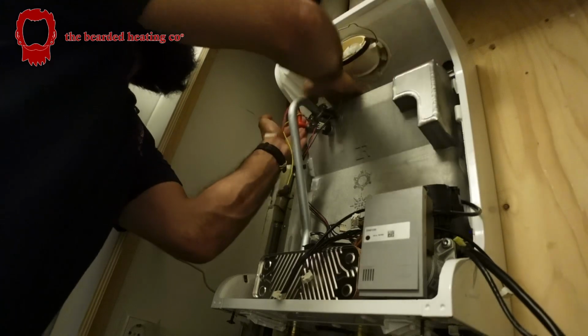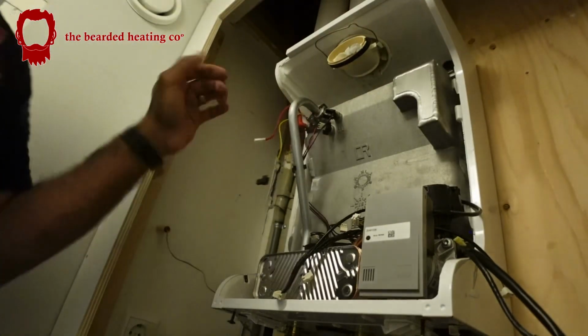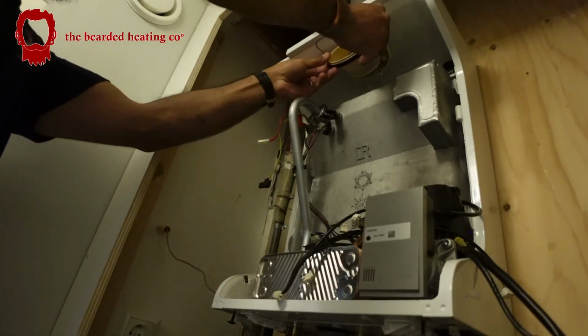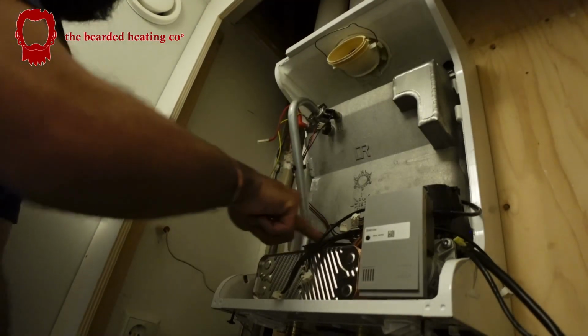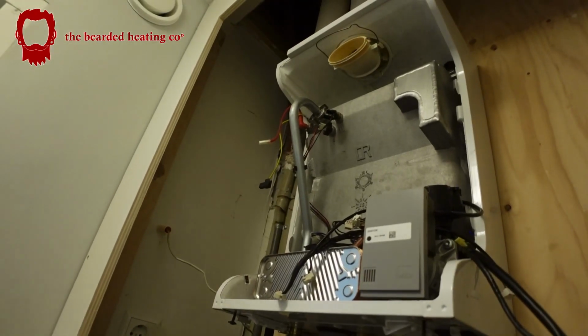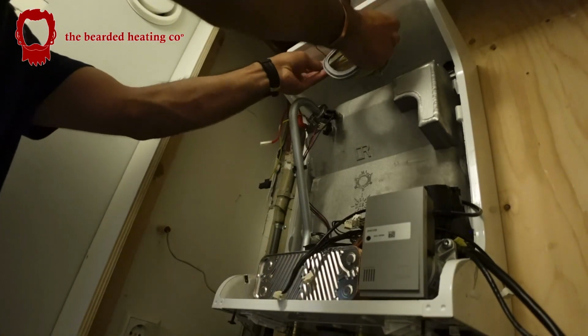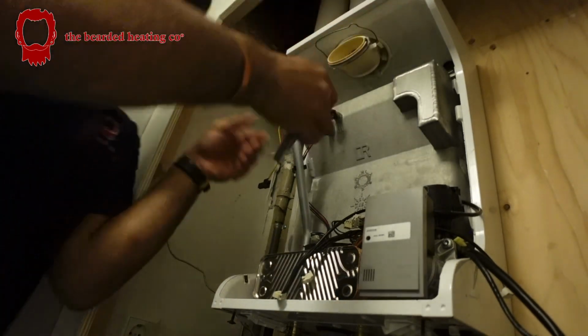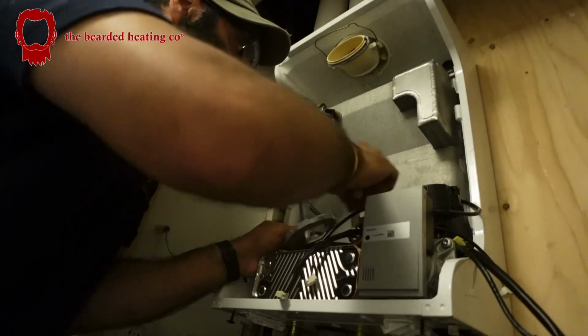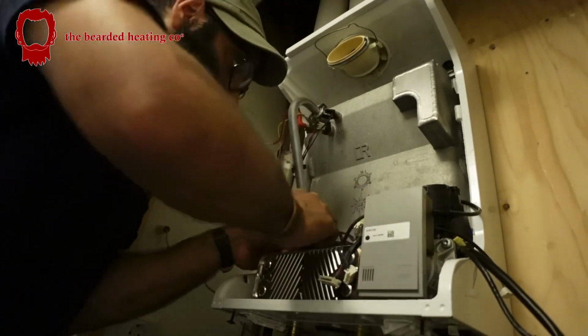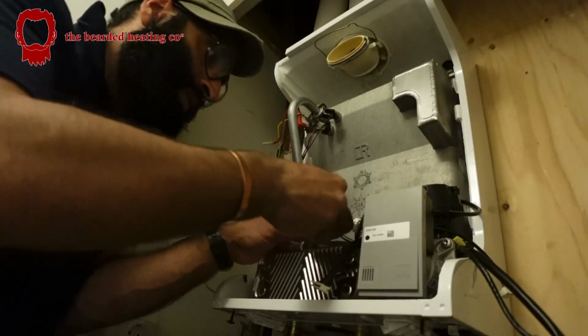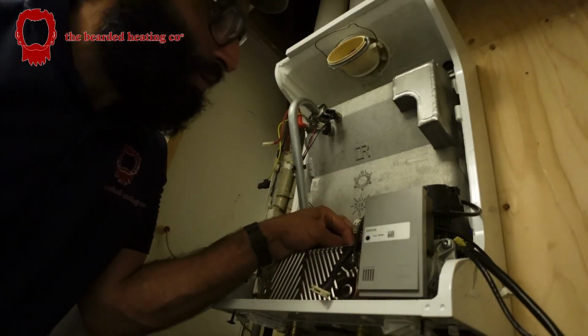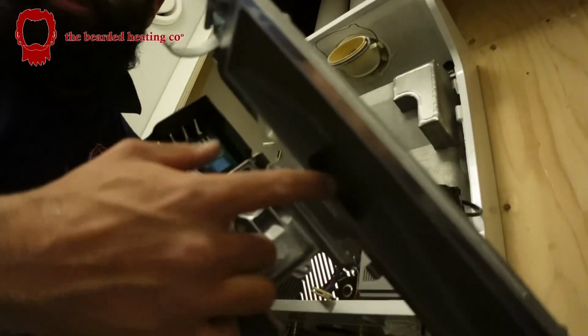That goes in there. Sits nice and snug. Perfect. Let's get that out. There's a new gasket. And obviously the sump gasket I've already removed. And here's the new ones. So that goes on here. There you go. New sump gasket. That's secure. Hall sensor for the cold water. Put that on. Just so that you all know, there is a non-return valve just in there, inside the air and gas mixture inlet. Always just check to see that that is free and moving.